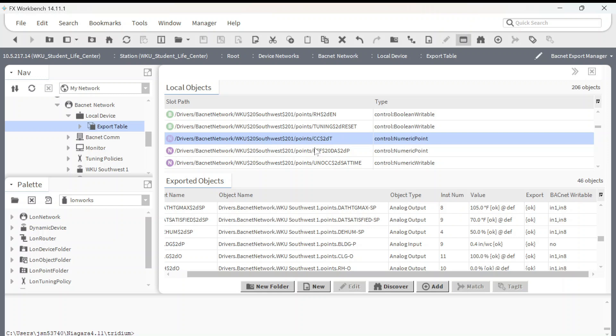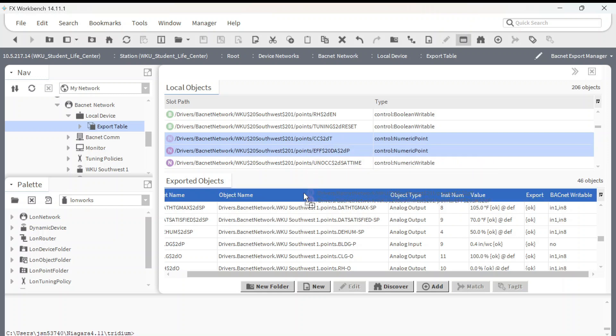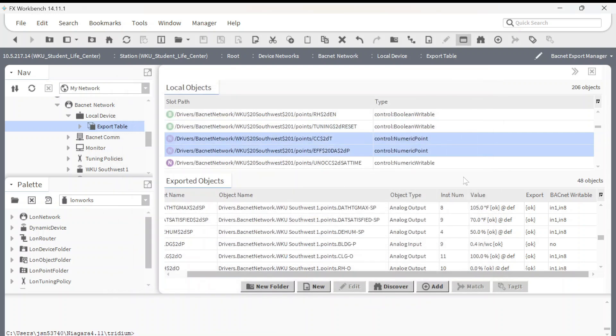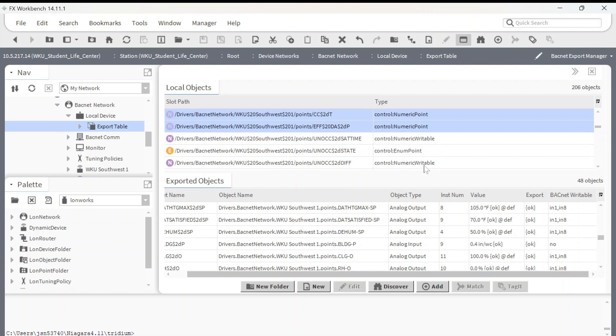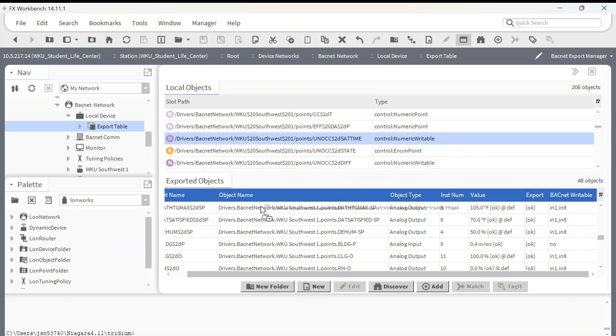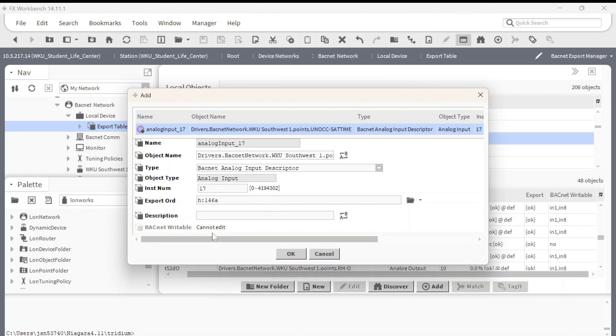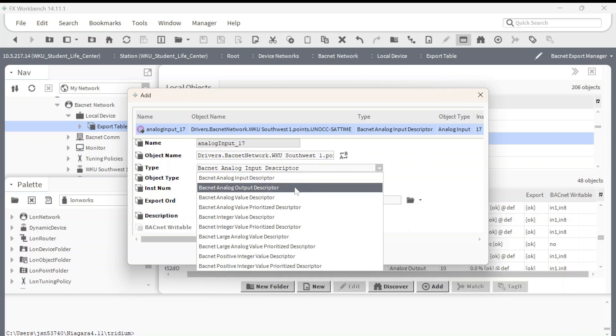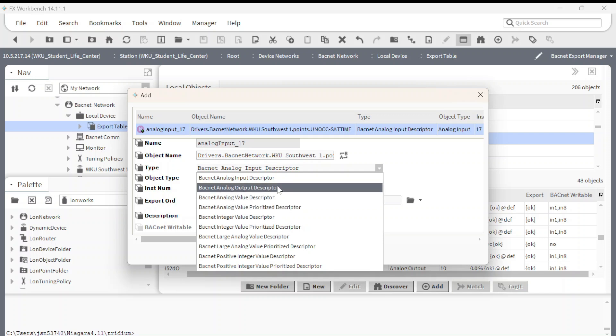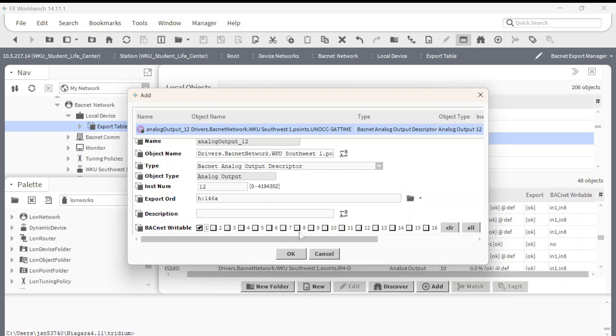You can see on the right-hand side of the screen on the bottom panel it'll tell you whether some of these are writable. Some points are labeled as writable and some are not. For points that are not writable I'm just going to drag them down and drop them into the export table — nothing special needed in the pop-up. But when I come to a point that is writable, I need to pay attention. When I pull it down to the table it gives me the pop-up window and I need to change the point type — from an input to an output.